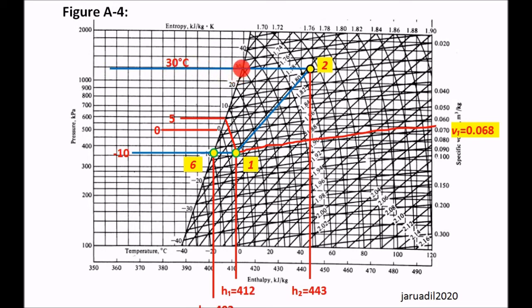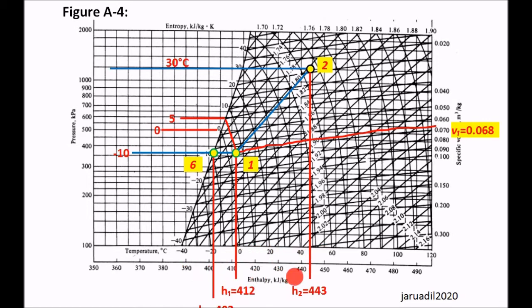From there we can read H2 as 443 kJ/kg. We read from the enthalpy axis — not from the temperature axis. The temperature labels are on one side, the enthalpy values are on the other. So it is straightforward to use the pH chart for finding 1 to 2. These are just approximations from the graph, but they are close — you would not estimate 440 or 450 because you can see the difference clearly.